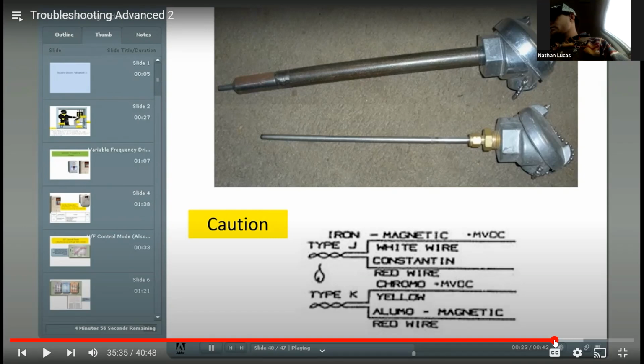The other fun thing to know about wires is the red wire is always the plus wire. The white wire with type J is minus, or the yellow wire with the type K. Also notice on type J thermocouples that white wire is magnetic. If you've got a little magnet probe like on the end of one of those little baby screwdrivers, the white wire should suck to that because it's an iron Constantan wire. Okay.